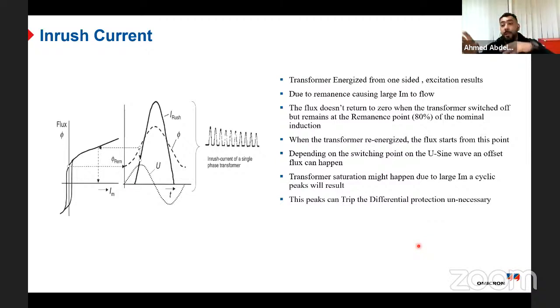This can cause what we call a power swing in our system. So what we do is close the high voltage circuit breaker for a certain moment, then I close the low voltage circuit breaker. This procedure may subject the transformer to overexcitation, because I'm energizing from one side. A huge current will flow in the iron core of the transformer, so it will increase something we call the remnant or residual flux, and a magnetizing current will flow in the transformer.